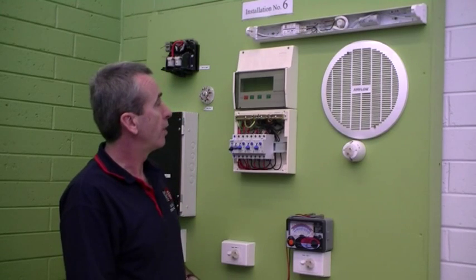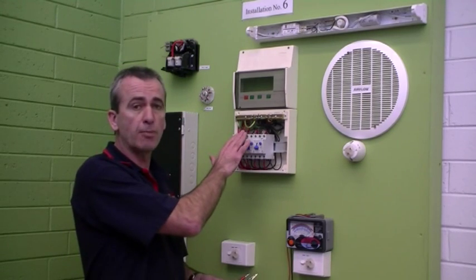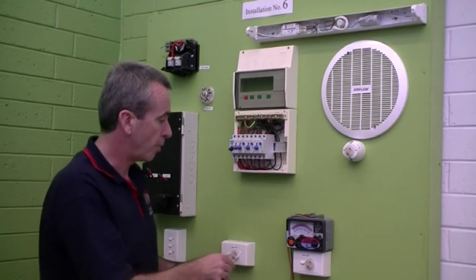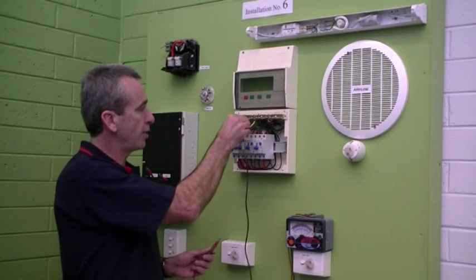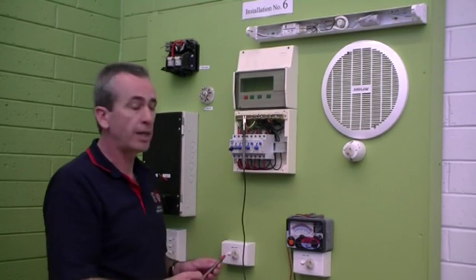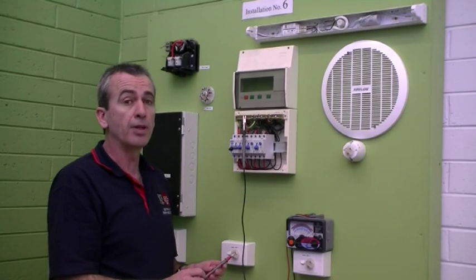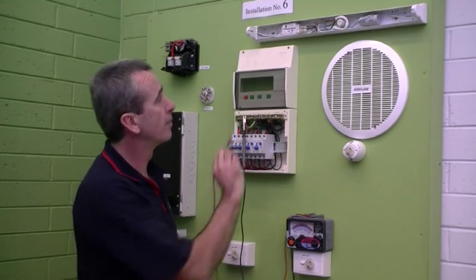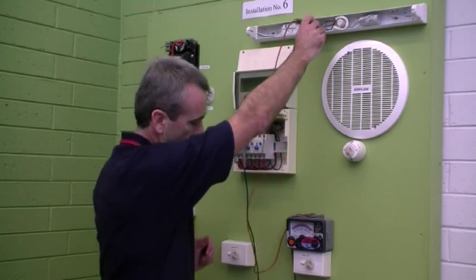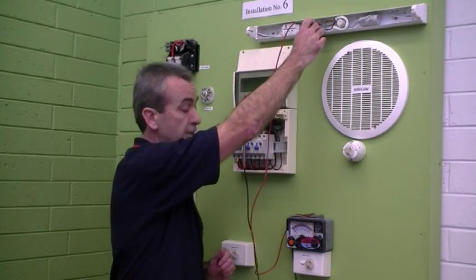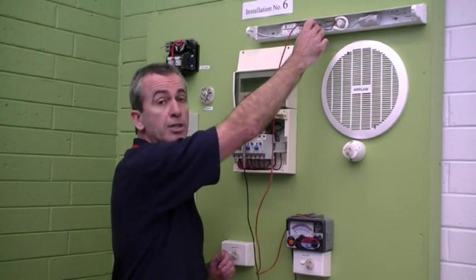I'll now test the resistance of the protective earthing conductors. That's the earth wires that are associated with electrical equipment. All of those earth wires are connected up to the earth bar, the switchboard. So with my meter, I'll put one lead connected up to the earth bar, and the other lead I'll take around to the other pieces of equipment that I want to check to make sure they are earthed. With the fluorescent light, the resistance is very low, about 0.05 of an ohm.